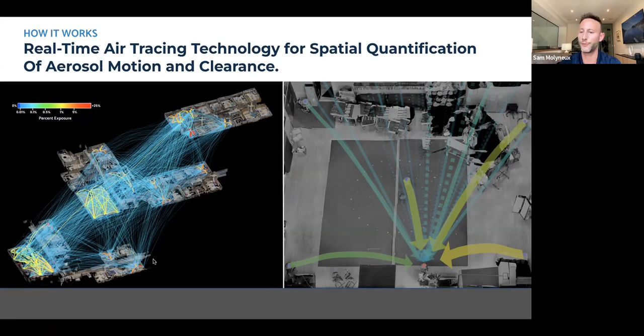Okay, so what is the validation of this type of technology, and how can we be confident in the measurements it makes? So the first thing I just want to bring up is a very simple decay graph. The simplest measurement that we want to be able to make in a room, for the effective air change rate and other equivalent metrics, is generating a decay graph for that room. What this comprises is release of your tracer particle quantity into the air over some time or volume of liquid tracer particle released, and then enabling that to build up, and then watching that decay through whatever ventilation and filtration mechanisms are in place. We care a lot, as I mentioned, about the 0.5 to 1 micron fraction being the aerosols that persist longest. And this decay curve is mathematically translatable using simple calculations to the ACH of the room, and then that metric can be transformed into that other set of metrics.